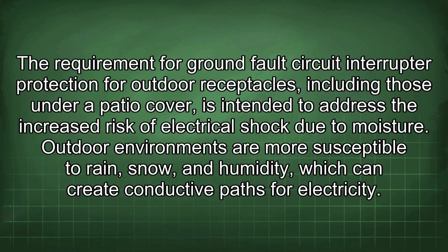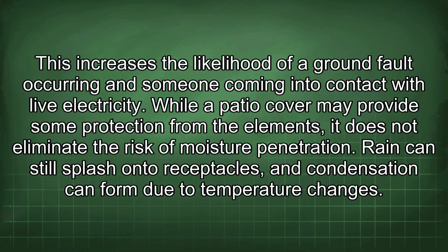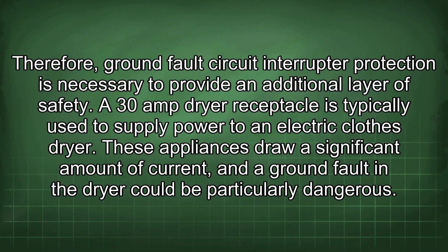The requirement for ground fault circuit interrupter protection for outdoor receptacles, including those under a patio cover, is intended to address the increased risk of electrical shock due to moisture. Outdoor environments are more susceptible to rain, snow, and humidity, which can create conductive paths for electricity. This increases the likelihood of a ground fault occurring and someone coming into contact with live electricity. While a patio cover may provide some protection from the elements, it does not eliminate the risk of moisture penetration. Rain can still splash onto receptacles, and condensation can form due to temperature changes. Therefore, ground fault circuit interrupter protection is necessary to provide an additional layer of safety.